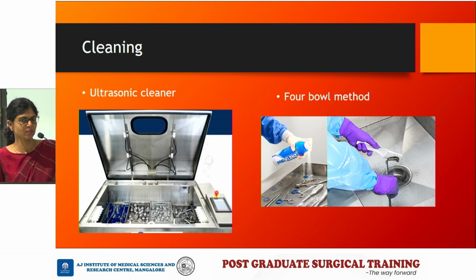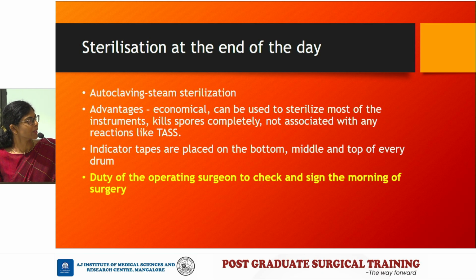And then finally it goes into sterilization. So autoclaving or steam sterilization is what is commonly used. Of course, it is the most economical. It can be used to sterilize most of the instruments that we use in the OT. It is completely sporicidal and it is not associated with any reactions like TASS. Now, to make sure that the sterilization is complete, we place indicator tapes, and I'll be talking a little more in detail when it comes to chemical indicators. They are placed in the bottom, middle, and top of every drum. And the duty of the operating surgeon is to check and sign before you even start your first case in the morning of the surgery.